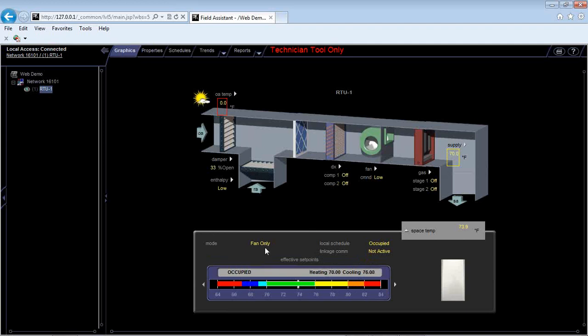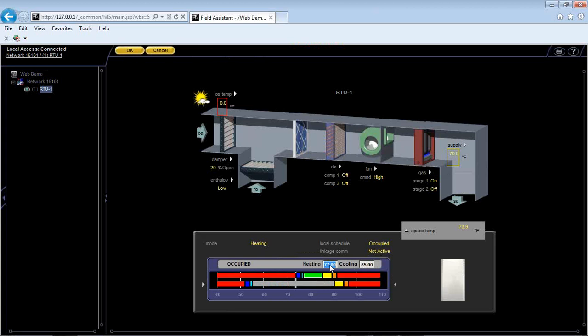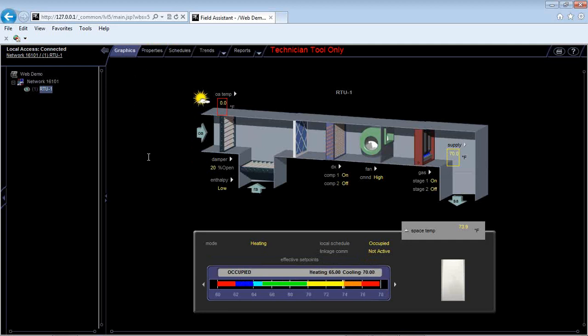Now if I give it a minute here, I'm going to go into heating mode. See how it switched to heating? Now you can see my gas stage went on. And with the 2-stage fan, I actually went into high fan because you need to go high fan for heat. Let's say I want to make sure the cooling runs. I can bump my set points back down to, let's say, 65 and 70. I hit OK. I've got my minimum run times built into the unit, so I still have to run my heating for a specific time, but I'm going to switch over from heating to cooling here in a minute.